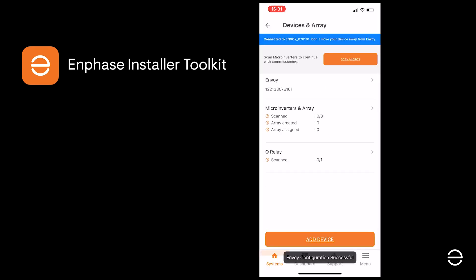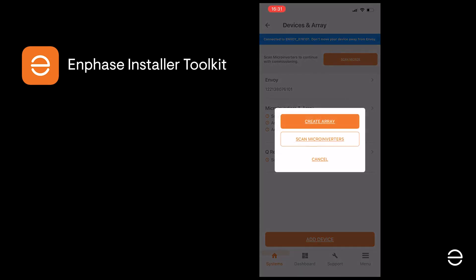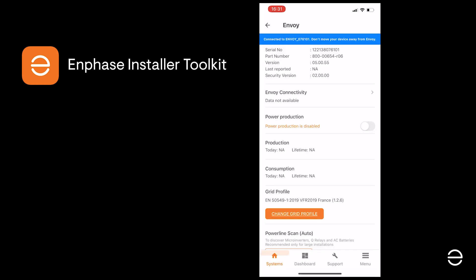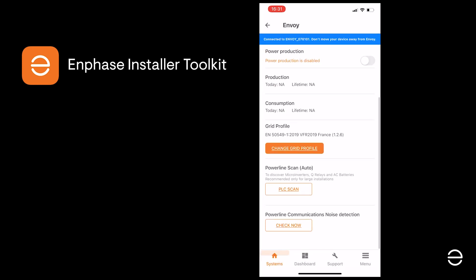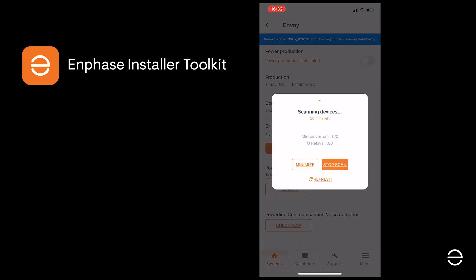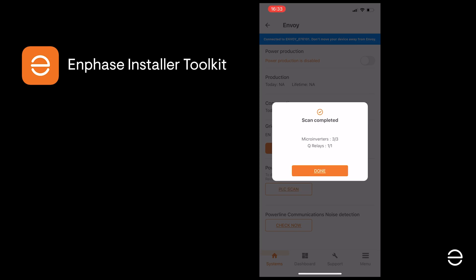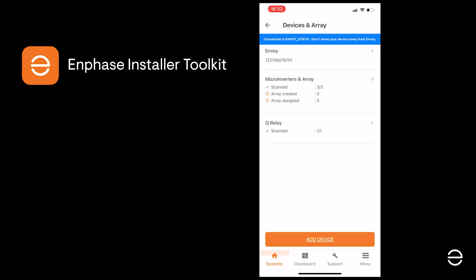The easiest way to create the array, since you're connected to the Envoy, is to let the Envoy do the work. Click on Scan Microinverters on the next screen, scroll down to Powerline Scan Auto and click on PLC Scan. The Envoy will then communicate with the ITK app and update the devices in the system. When the scan is complete, check that all the devices have been found — in this example three microinverters and a Q-Relay — then click the back arrow at the top of the screen to proceed.